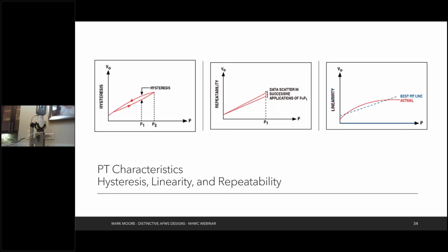I promised earlier I'd talk about hysteresis, linearity, and repeatability. Again, I'll try to be brief here. But hysteresis is basically asking whether the relationship between the output signal and the actual pressure on the PT is the same going up as it is going down. If you are familiar with discharge rating curves, which is the relationship between stage and flow at a creek, you also have to consider hysteresis, because as the water level goes up versus going down, you actually see different measured flows at the same stage elevation. You can see that with the PT as well. You can see a different output if the pressure is going up versus going down at the same pressure because of hysteresis effects.